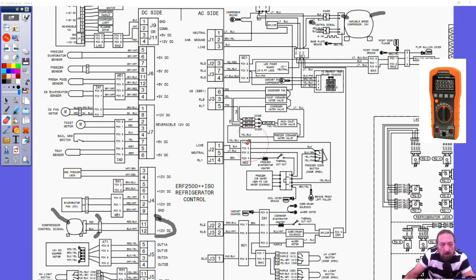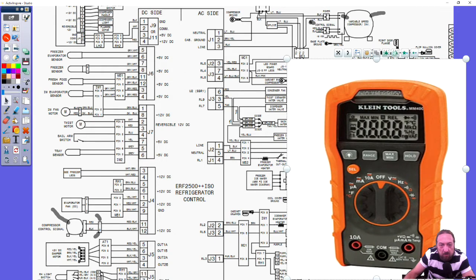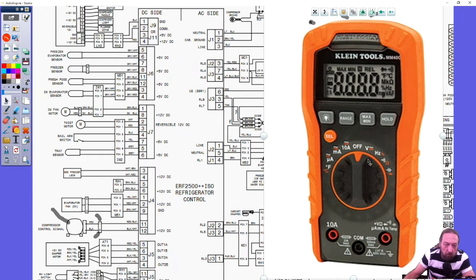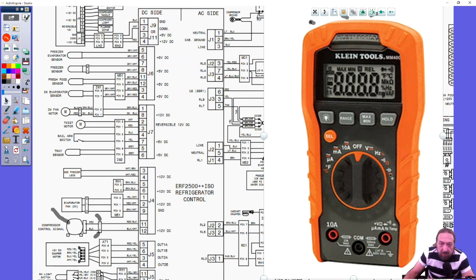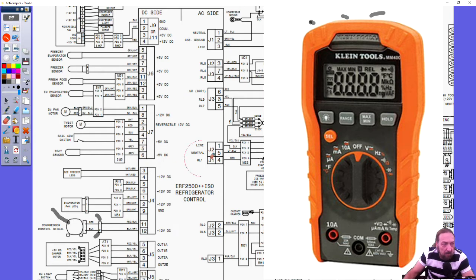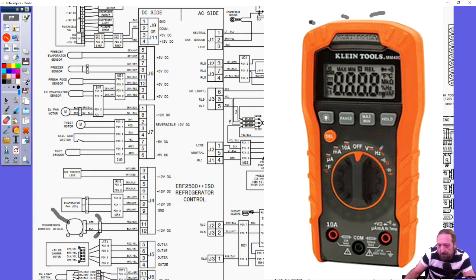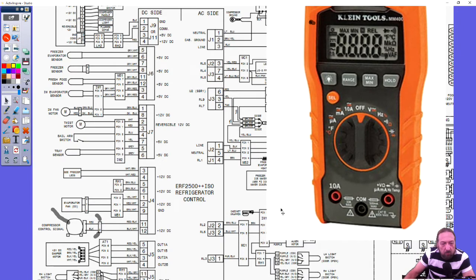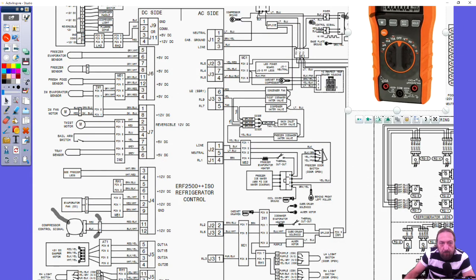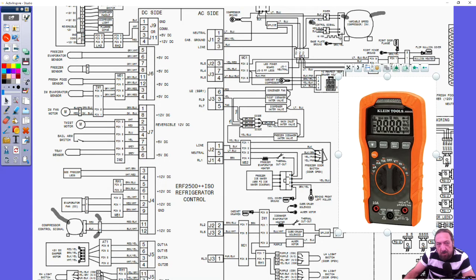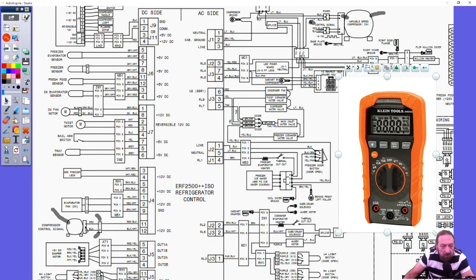Frequency? You would check in frequency. So you'd have to have a meter that has the ability to check frequency. I have this exact meter and I like it because it does so much for so little. It's like a $35, $40 meter. It has a capacitor tester, it's got ohms, but right here it's got HZ which is hertz. And if you can see my mouse is around it, that's the hertz for the frequency. And I think it's like 240 hertz or something like that is what's supplied to that unit. Coming off this board, there's a frequency, there's AC voltage, and there's DC voltage. The AC voltage is here, the DC voltage is here. If you're checking it at the board, it's the same thing as the compressor control signal down here. It's 12 volts.